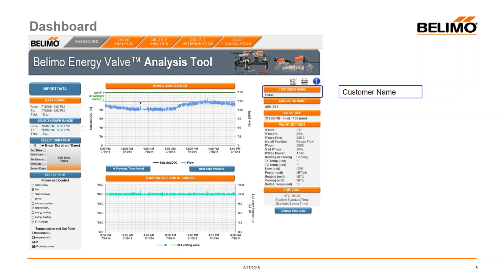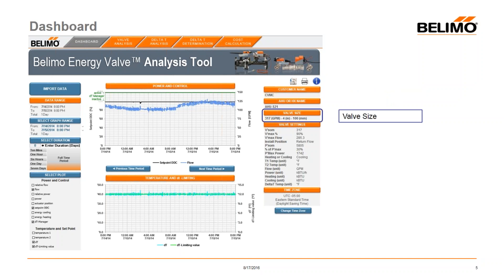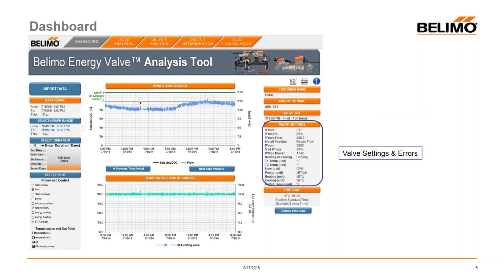Upon importing data, a pop-up screen asks you to enter the customer name or job name for the data set, and an air handler unit name or heat exchanger name. It will pull the valve size showing gallons per minute and valve size, and display valve settings. If any unit of measure changes throughout your data set — for instance, if it was set to Fahrenheit but someone switched it to Celsius — you'll get an error message with the date, time, and what it was changed to, as the data will be corrupted.